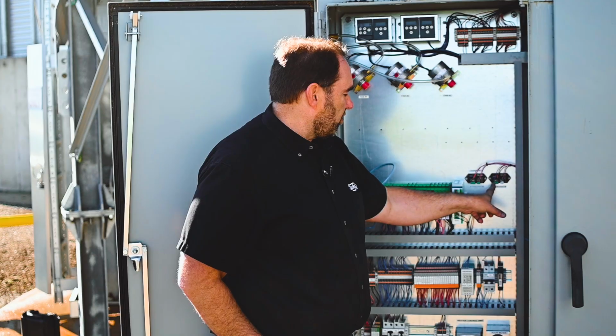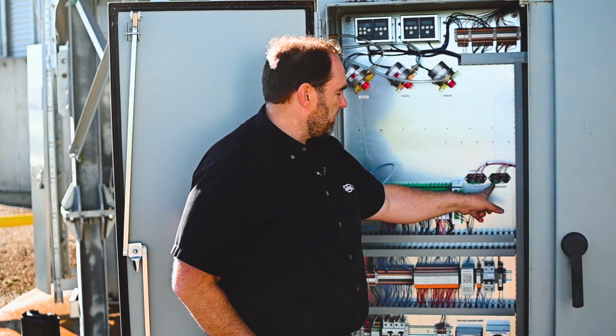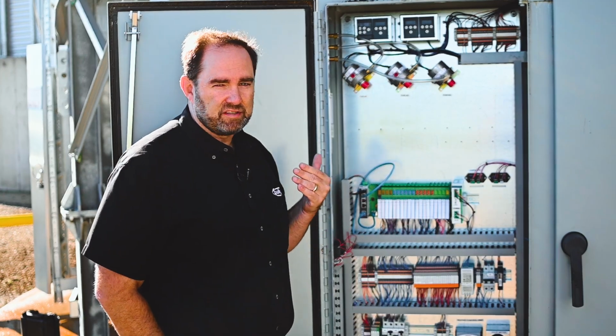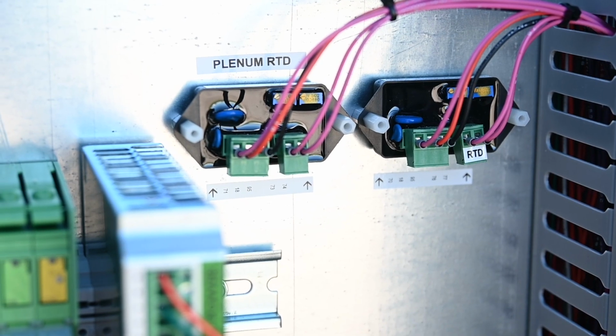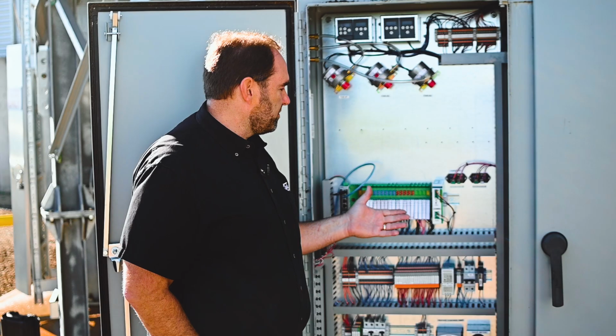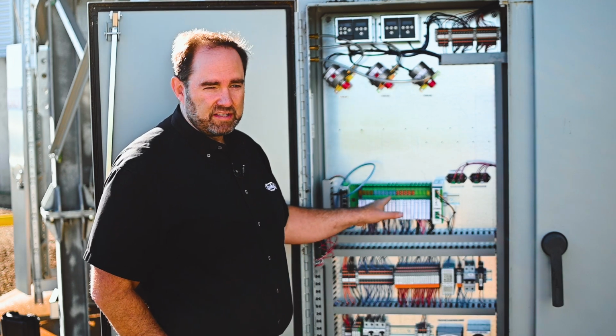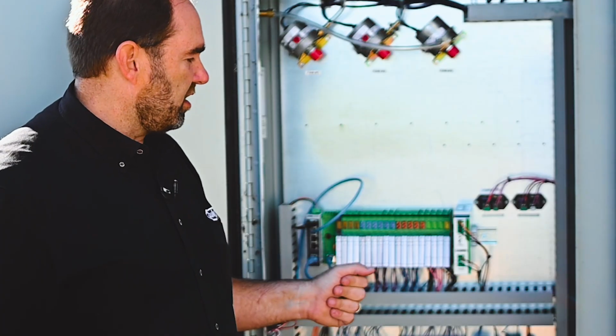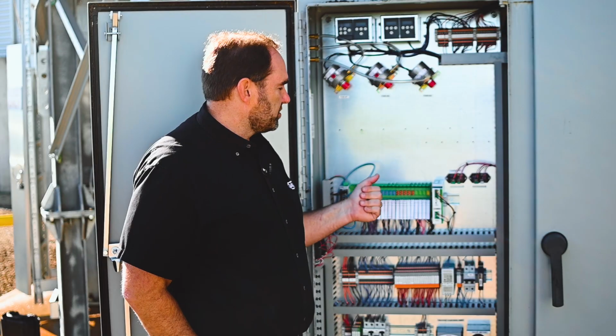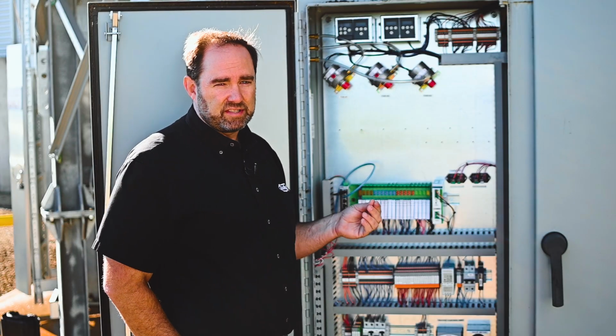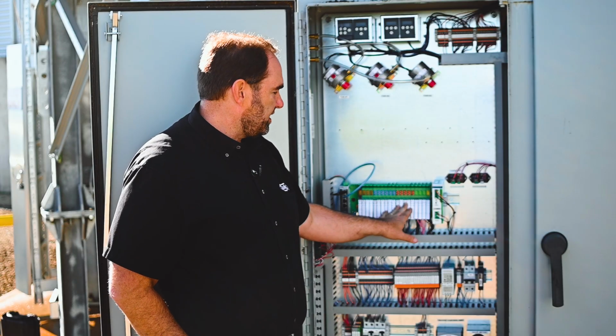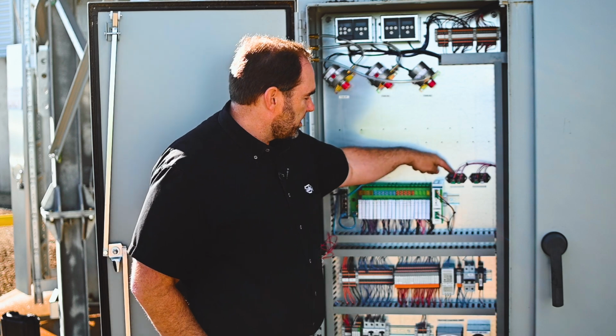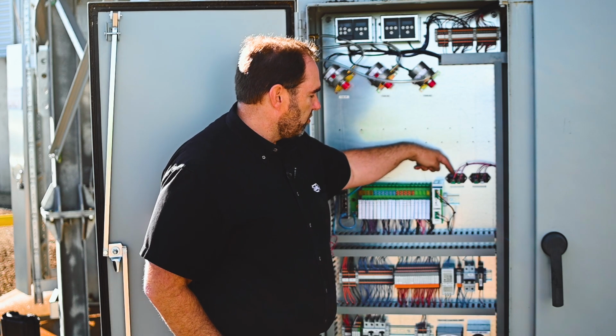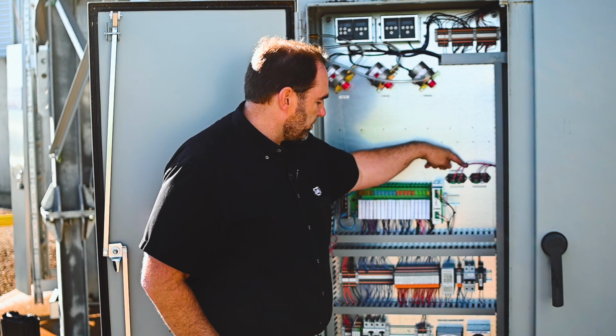Over here we have RTD transmitters. So what these do, we have RTD sensors. RTD is resistive temperature device, so just think of it as a thermometer. And there's one in the plenum that tells the PLC how hot it is in the plenum. There's also one for the grain columns to tell it how hot the grain is. Those RTDs work off of change in resistance or change in ohms, and the PLC needs to see a change in voltage. So these transmitters translate resistance or ohms into voltage is what their function is.